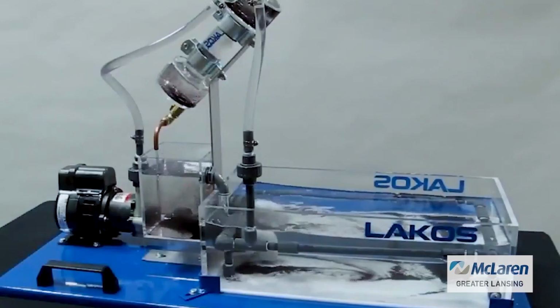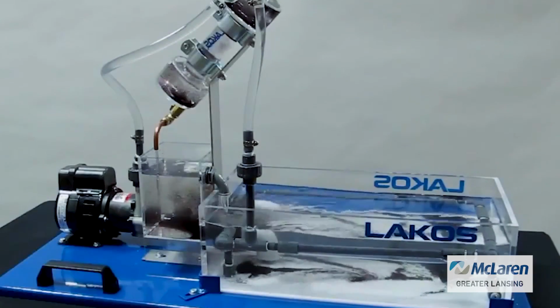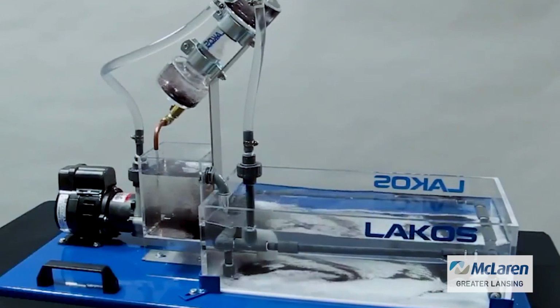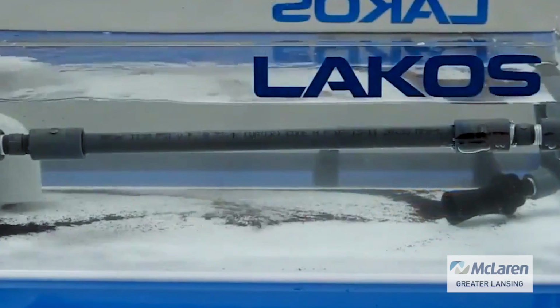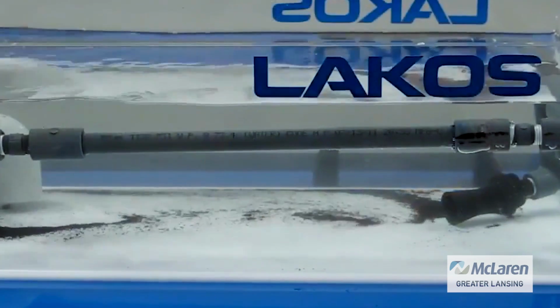Do you guys ever look at that media, that part of your humidifier? If you pull it out and look at it, it's all crusty, right? It's a bunch of minerals. If the evaporative process happens, you drop out of suspension the dissolved solids. They collect on the pad. Same thing happens in the cooling tower. That's why you do a blowdown, right? The water treater is going to do a blowdown.